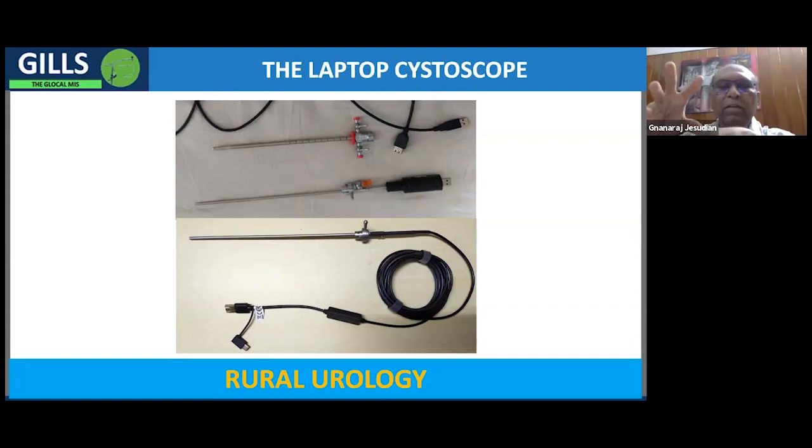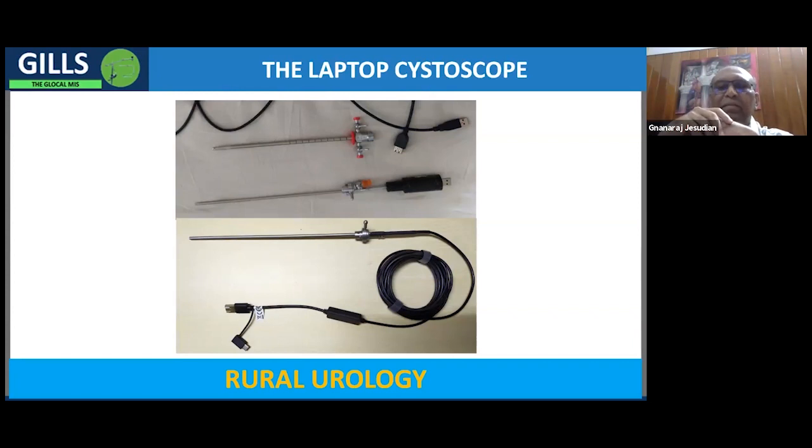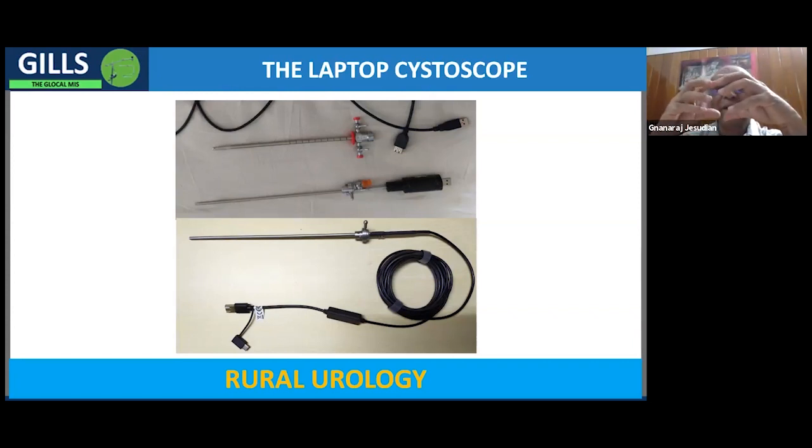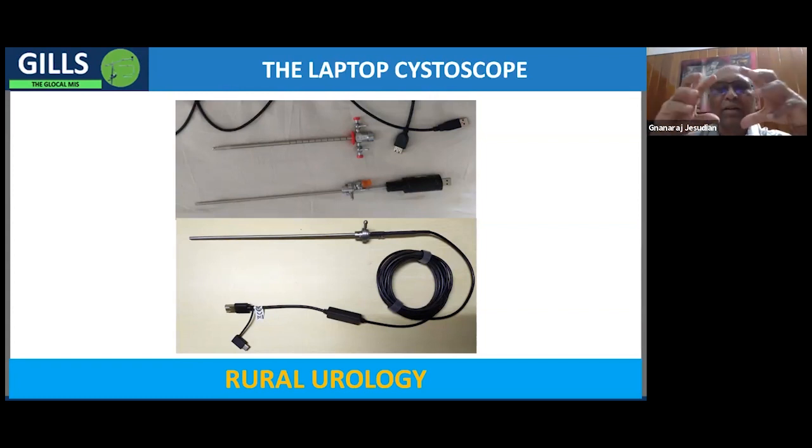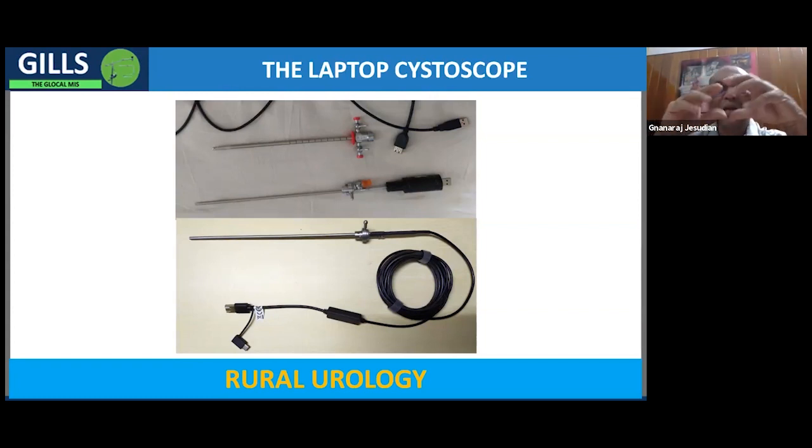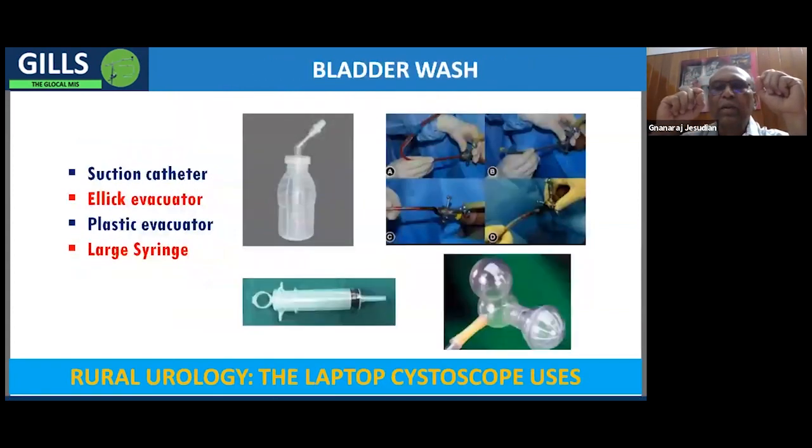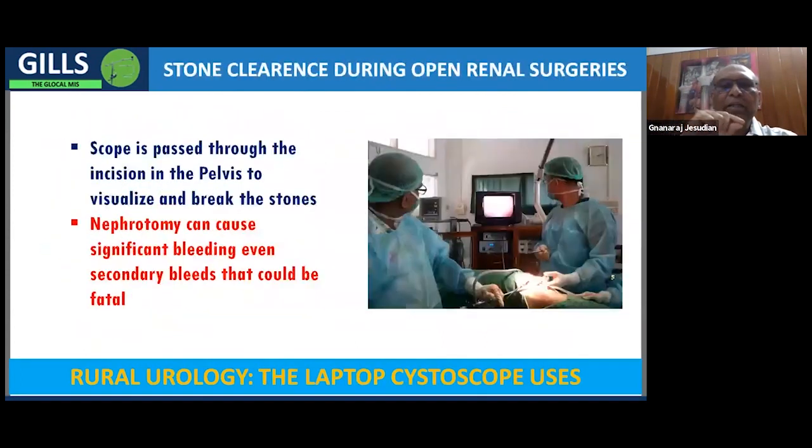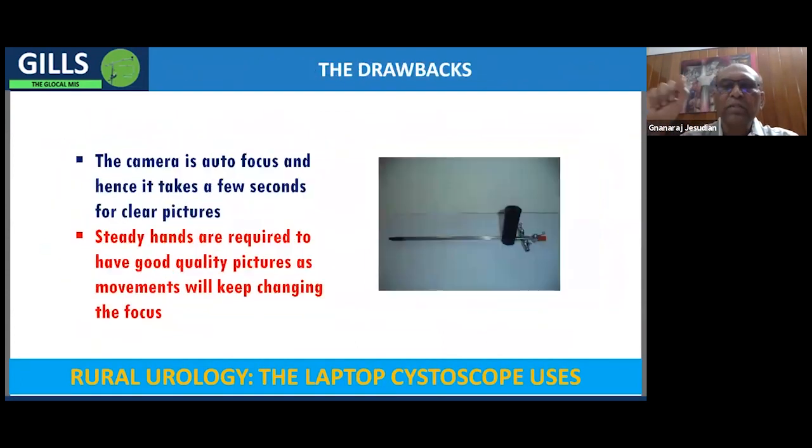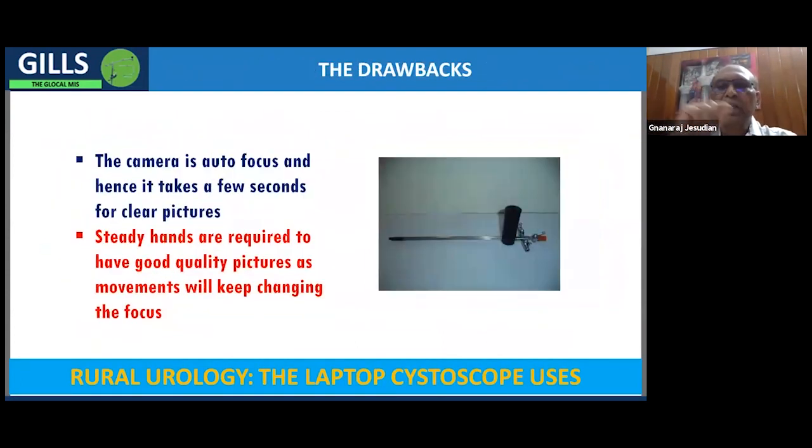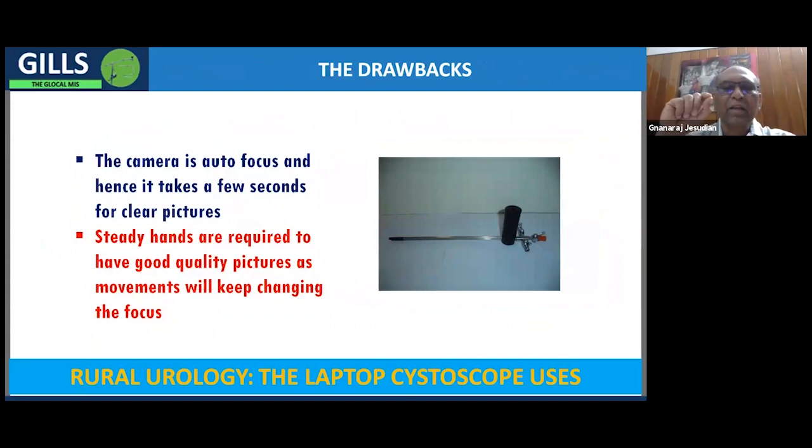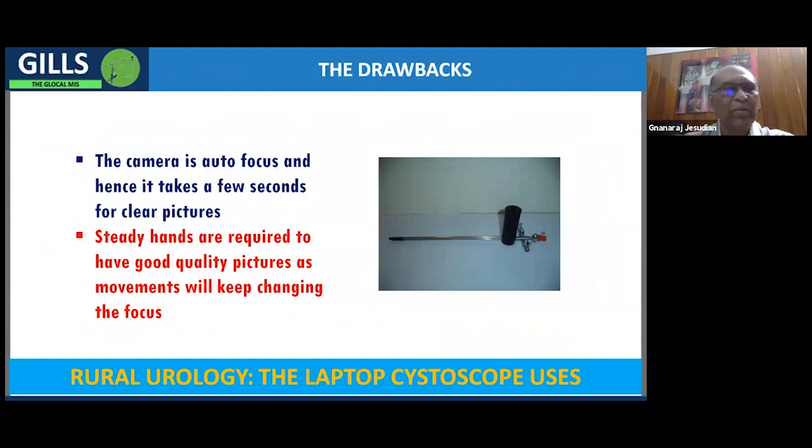These are all autofocus cameras, so it takes a little while for the mechanism to focus and give sharper images. So you need to be fairly gentle to do these procedures. You need to slowly do the cystoscopy and the stenting and other things. But it's not a major problem because anyway it's good to be gentle when you're doing all these procedures.